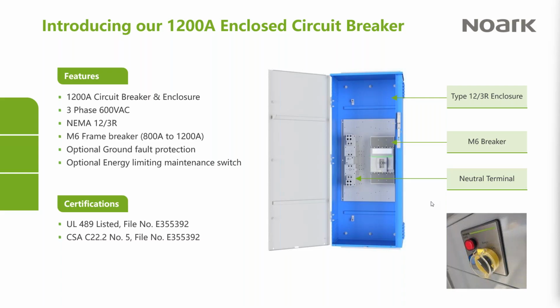Fantastic. I know that we are going to touch a little bit on ground faulting later, but there is just a question here about what's being used for arc flash reduction on the 1200 amp specifically. Right. Our terminology for that is an energy limiting maintenance switch. And the accessory for the M6 breaker is all passed through UL. We're just working on the final stages of putting it in production. So that's going to be called an ELM 20, and it'll be available as an accessory to the M6, and of course will be able to be included in the enclosed breaker. Fantastic. Thank you for providing those details.